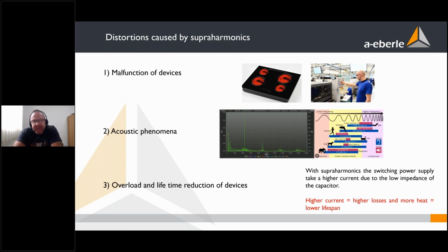And one of maybe the worst disadvantages of supraharmonics is the overload of other devices and the reduction of lifetime. So often with high frequencies, the current increases, so the heat and the losses increase, and this often means, in the end, a reduction of the lifetime of the device.